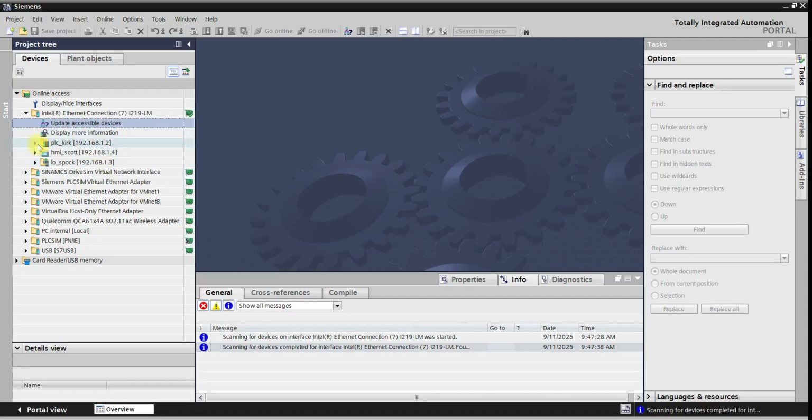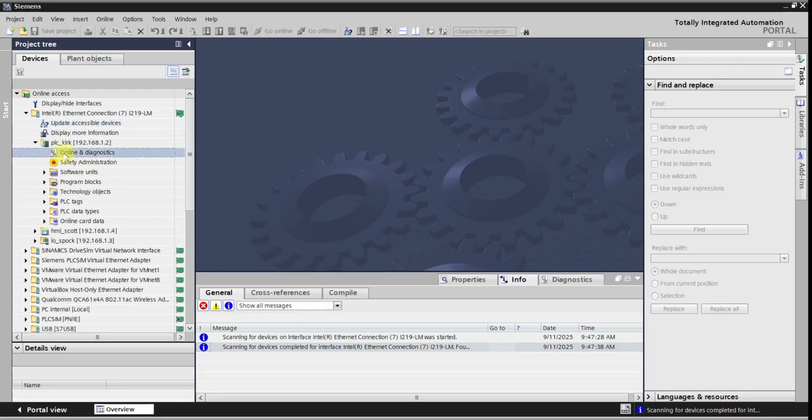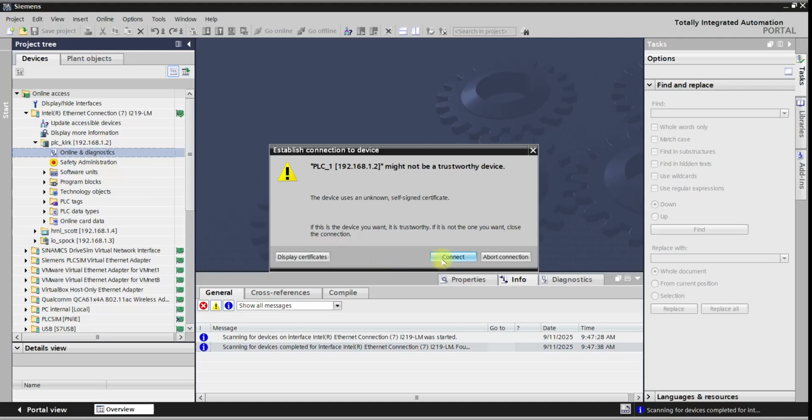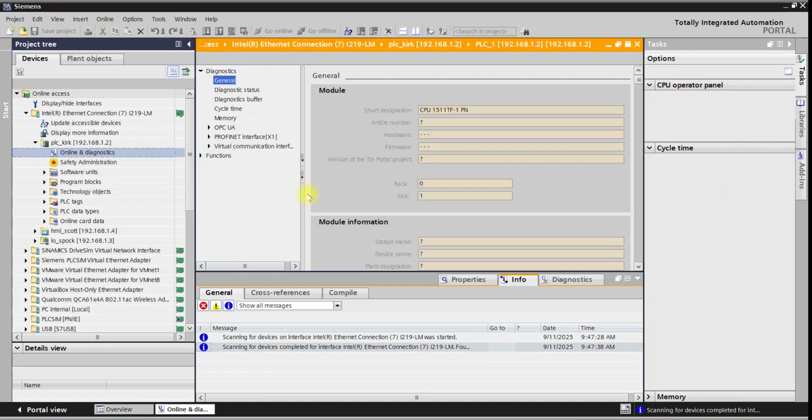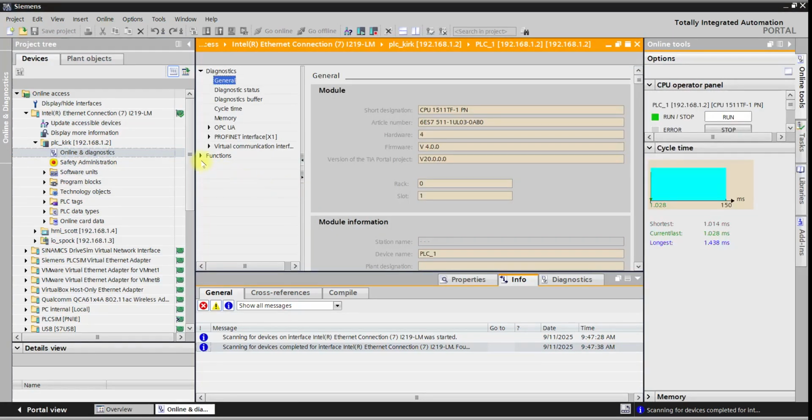If the times aren't right, then what happens is all your display values on the HMI show the little warning triangle that it can't get the data. And you always get this warning the first time you connect.